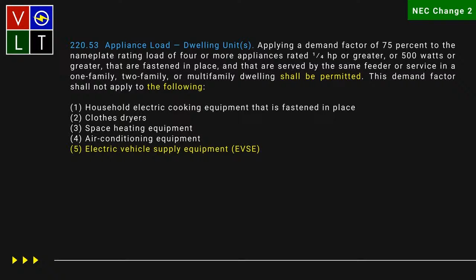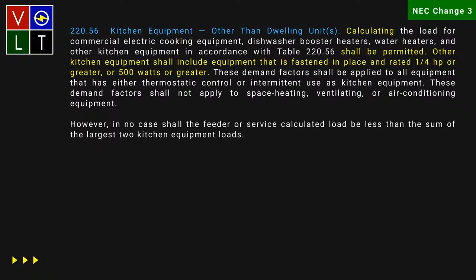If I go back here and look at the fixed appliance load, you see right here where it says 4 or more appliances rated 1/4 horsepower or greater or 500 watts or greater. Same language. The only difference is this is where I'm doing a commercial calculation, like for a school or a restaurant.